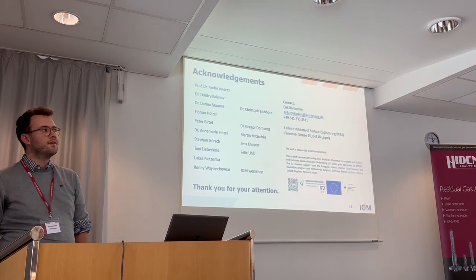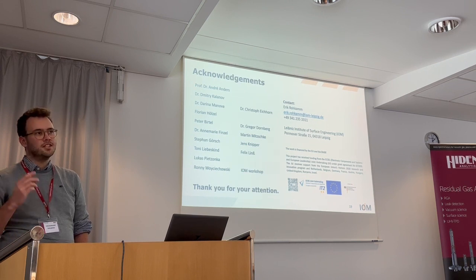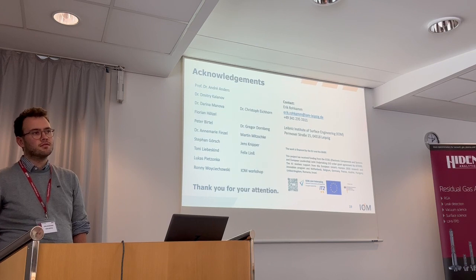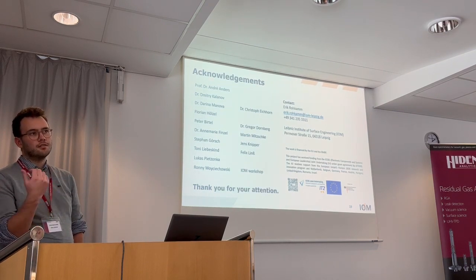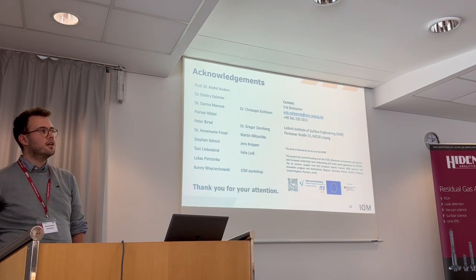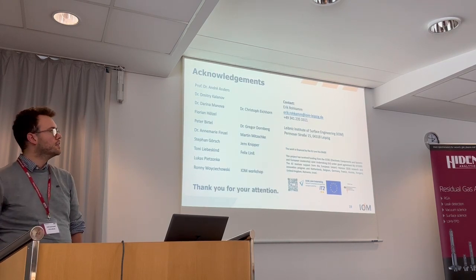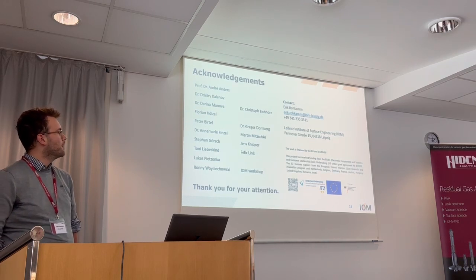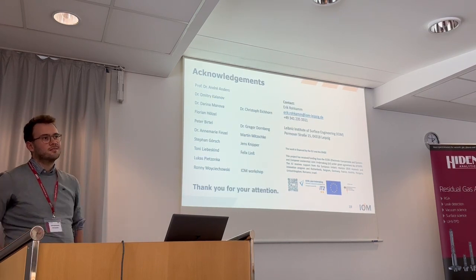What we see is that we have to replace the detector every 2 or 3 years, because you can see, of course, some degradation. But actually, there are very small amounts of fluorine entering your ESMS, passing the mass section and the energy section. So I think it's not that big a problem, but actually I cannot compare it to other cases because we're always using fluorine gases.